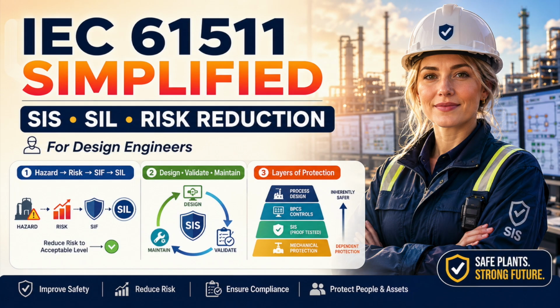You are not designing a trip. You are designing a controlled response to a hazardous process condition. You are making a promise that when normal control fails, when an initiating event develops, and when the process begins moving toward danger, the safety instrumented function will detect the condition, decide correctly, and drive the plant toward a defined safe state within the available process safety time. That promise has to remain valid through design, construction, commissioning, operation, maintenance, modification, and eventual decommissioning.